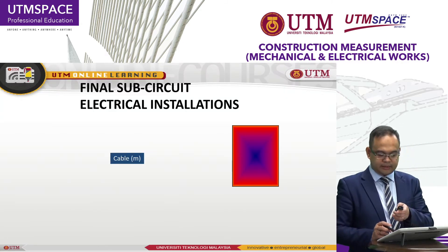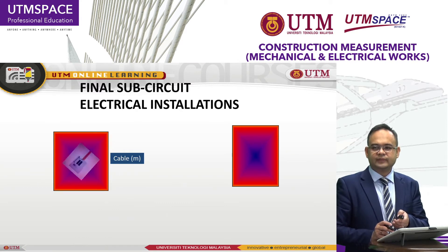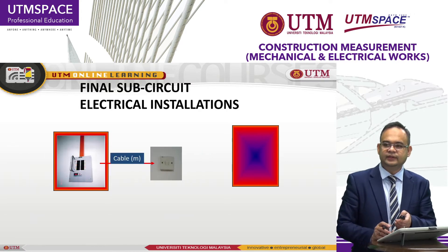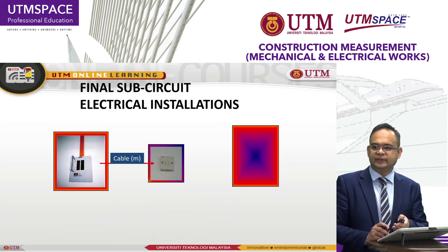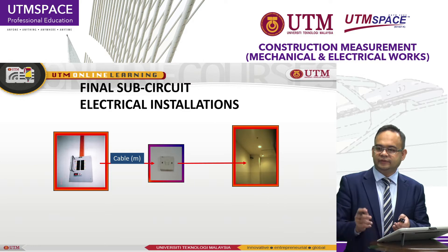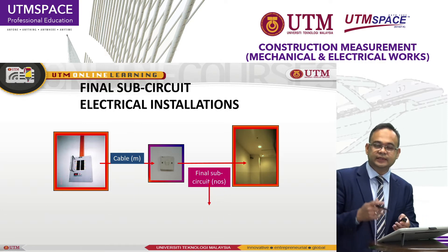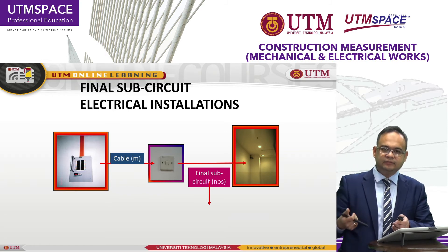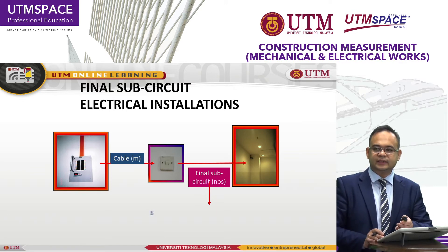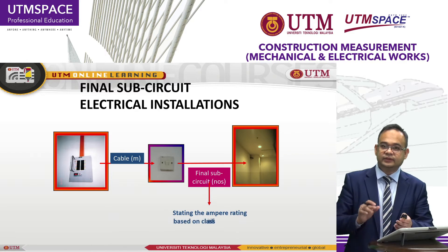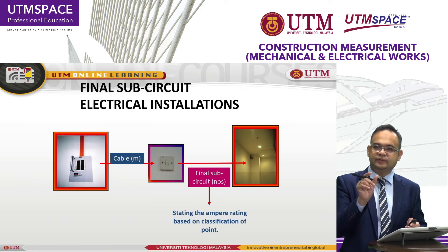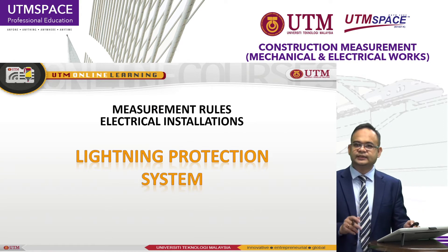This is just an example of the final sub-circuit. Next, I will show you. This is from the DB — you can see here — connected using cable for the supply to the switch, and from the switch to the lighting and also for the ceiling fan. We use what we call final sub-circuit, measured in number. For example, you have two switches: one final sub-circuit number one, one final sub-circuit number two — which is two numbers of final sub-circuit. You need to state the ampere rating, type of supply, and also the size of the cable and all related accessories.